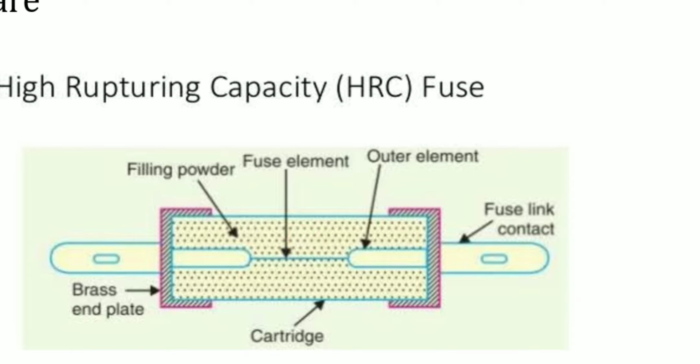Next thing is the operation, means how it is going to operate. Whenever an overrated current comes, when will it come? During the fault condition. During the fault, for example, we'll take a short circuit fault. Short circuit fault means an inrush of current will be there, nothing but overrated current. So when the overrated current flows through this fuse element, the element is going to get melted completely and vaporized, nothing but vapors are going to be generated.